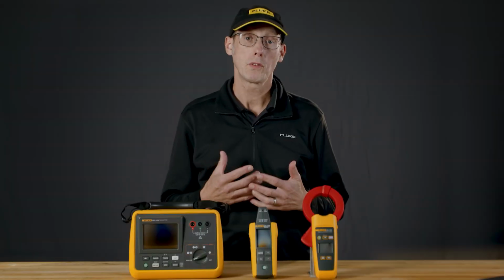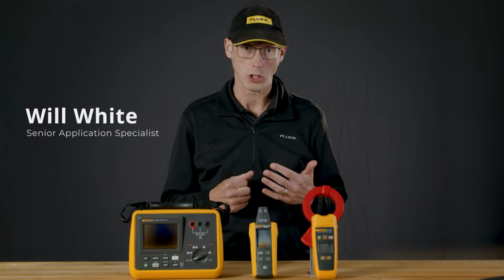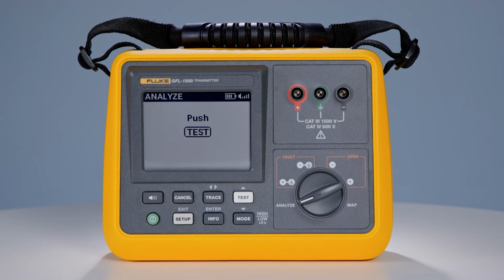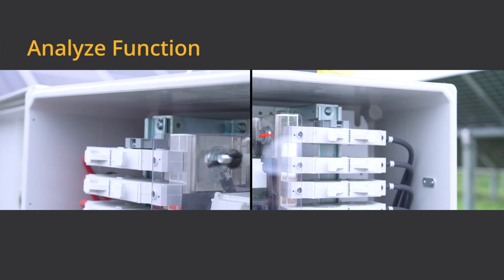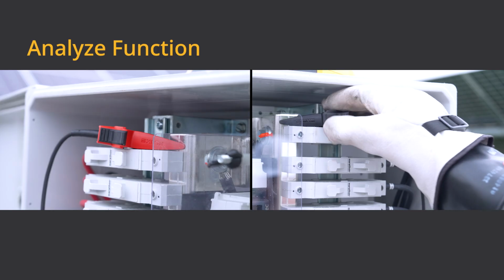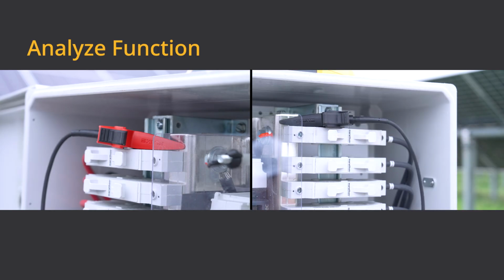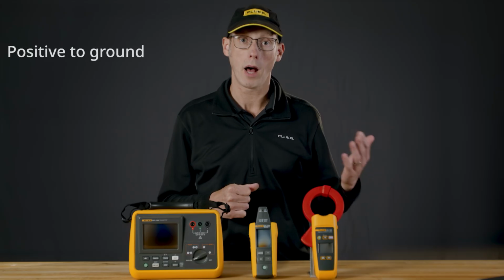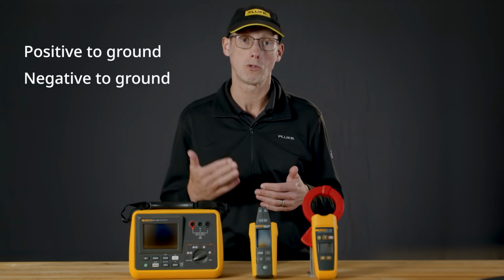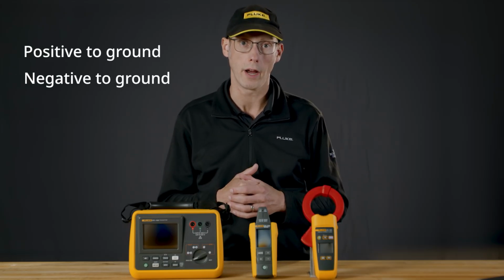The GFL-1500 has several different functions. The first one is analyze. Analyze measures voltage between the positive and the negative of our string of PV modules to measure open circuit voltage. It will then measure from positive to ground and negative to ground and check for voltage there.